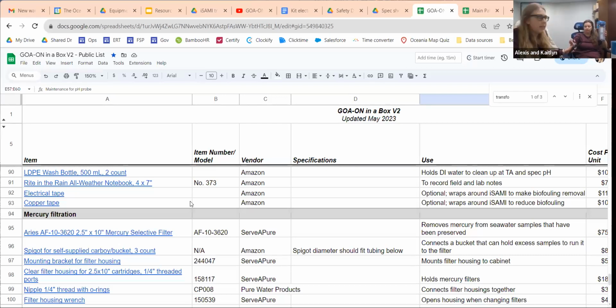There are a couple of maintenance pieces. The filter housing needs an O-ring, so we've included that. There's also some silicone lubricant to apply to the O-ring to create a watertight seal, so you won't have any issues with water coming out the top. To change out the filters, which we think should be good for quite a long time, again, we're not having a lot of mercury in our sample, we're including two filters. You'll be able to tell when those filters are going out because your test strips will start reading mercury again.